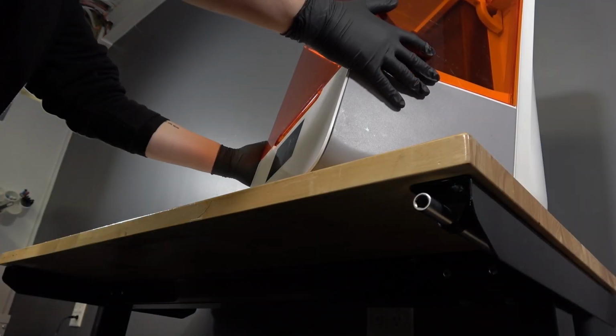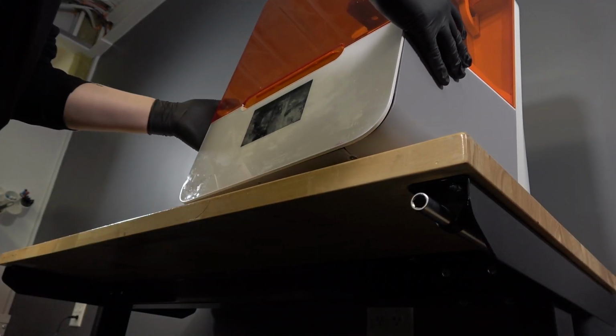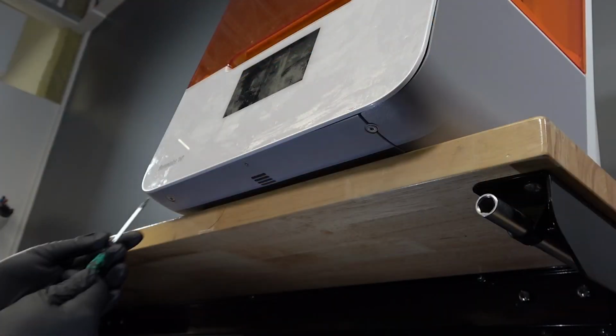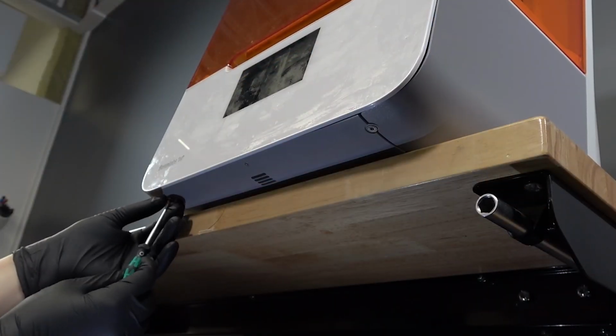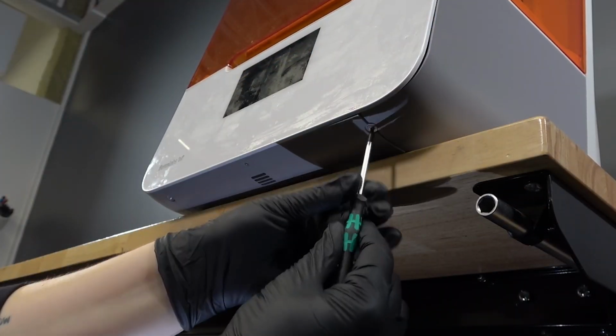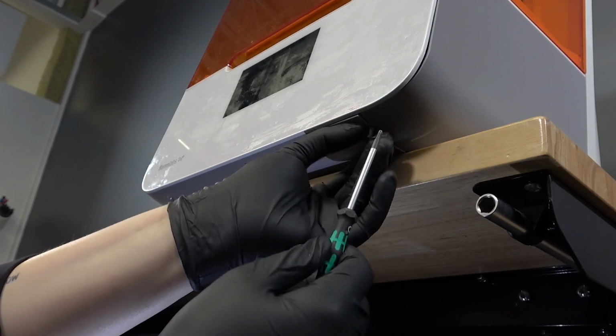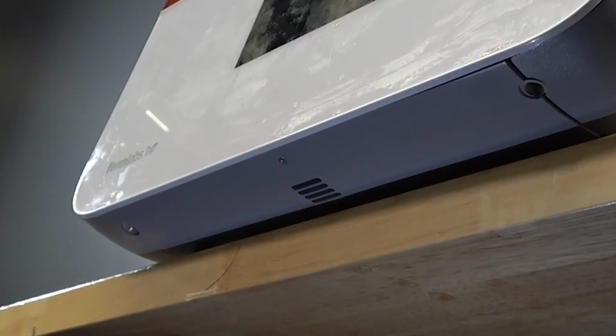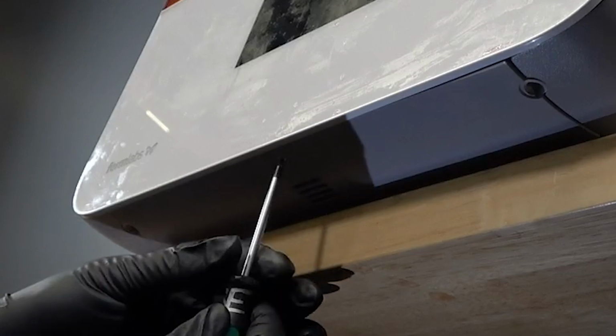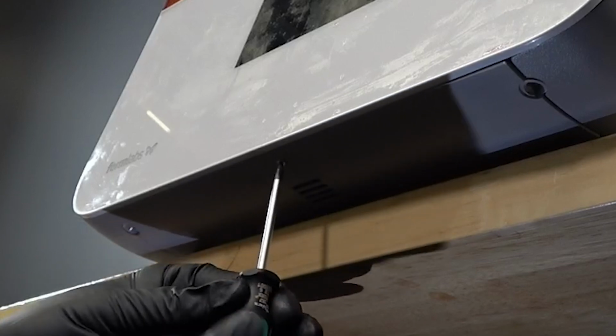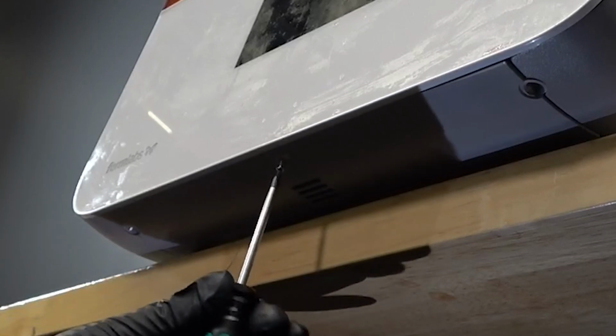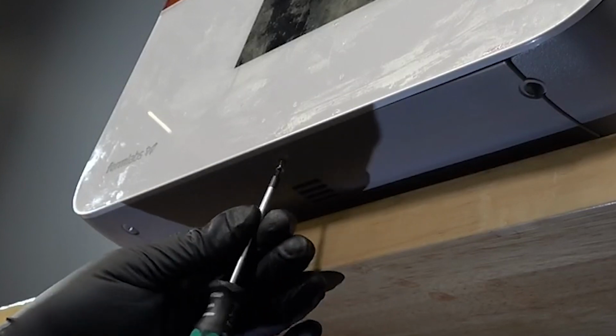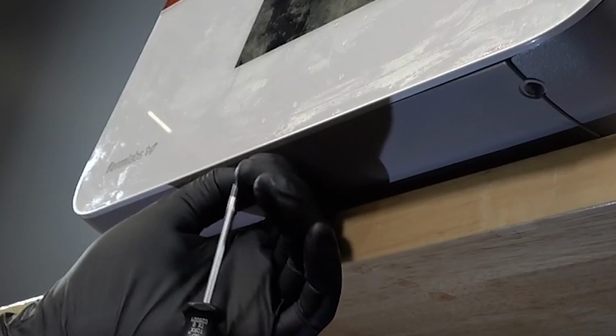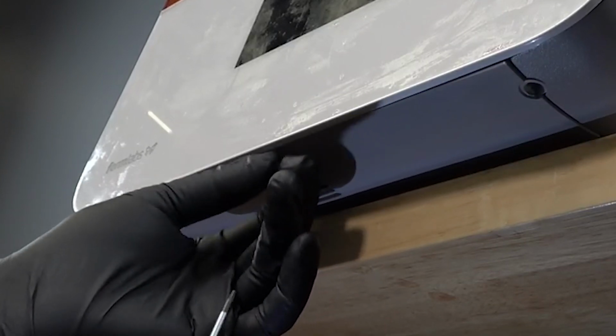Bring the printer to the edge of the work surface to reveal the screws underneath the front of the printer. Unscrew the two 2.5mm hex screws on the front of the bottom of the shell. Set those screws aside. Depending on the date of manufacture, your printer may have a third screw located between the two 2.5mm hex screws. The third screw is either a T6 Torx screw or a Phillips screw. If this third screw is present, remove it and set it aside.